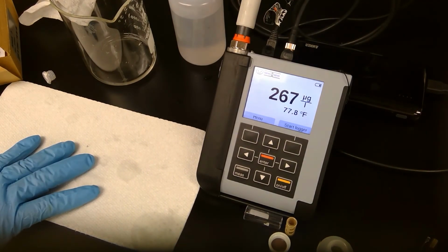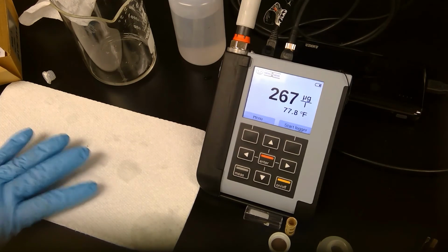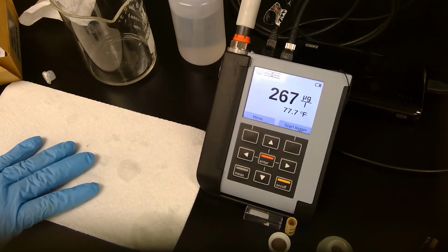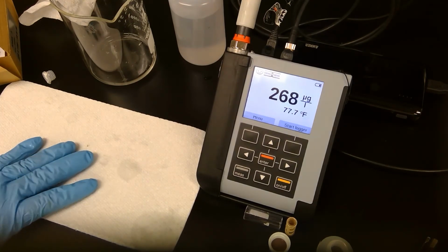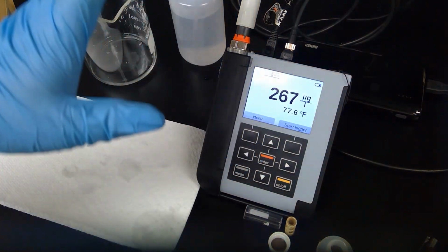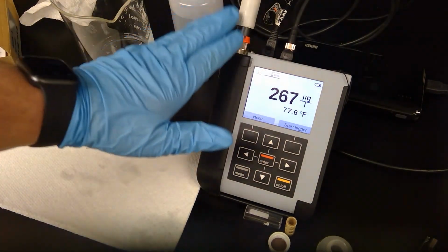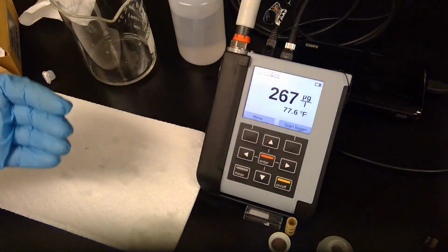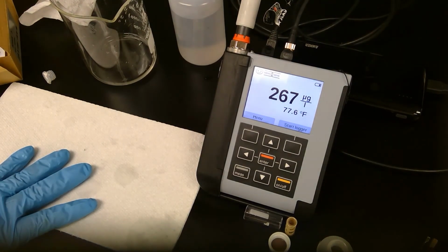A lot of times what we'll do is we'll recommend that if you're going to do a PM, do it later in the day, do your membrane electrolyte replacement, go and do your membrane reset, and then let it run overnight connected to power, so the next day you can come in and actually do the calibration.